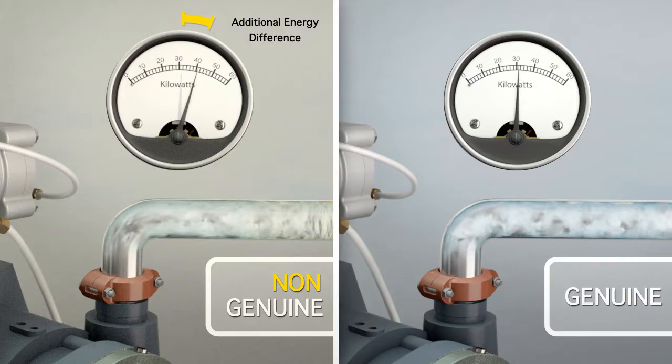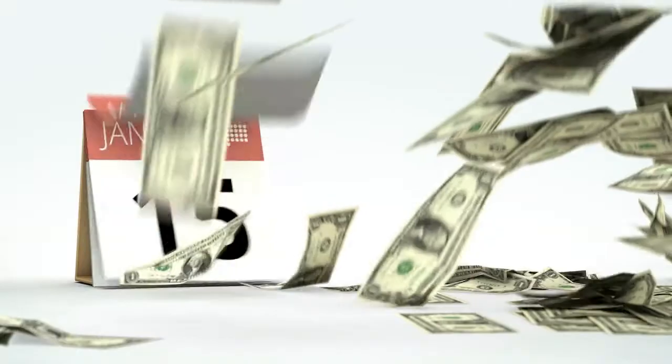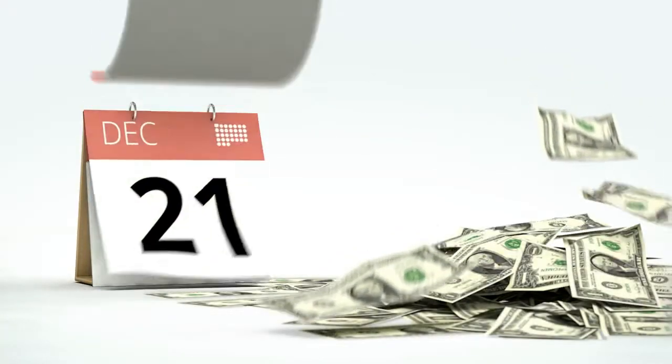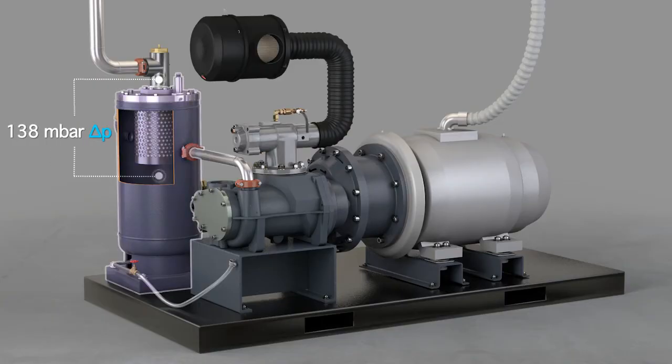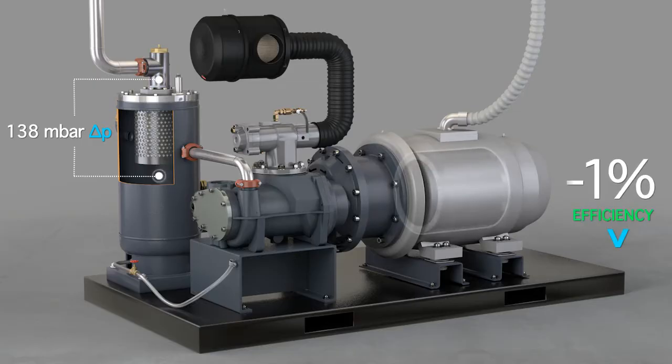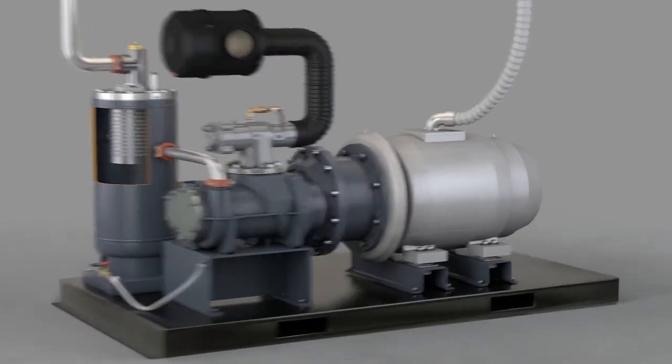Multiply this extra power requirement across the life of the filter element and costs soon start to accumulate. As a basic rule, for every 138 millibars pressure difference between the pressure vessel and the delivery port, your motor becomes 1% less efficient, adding 1% more to your running costs.